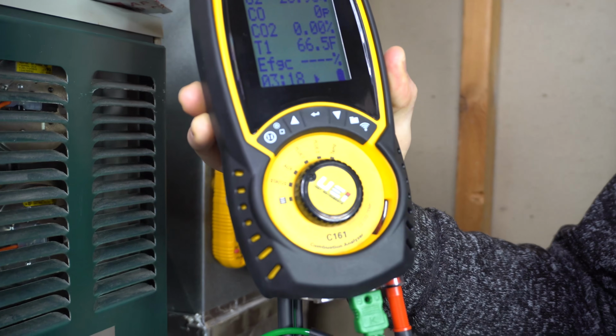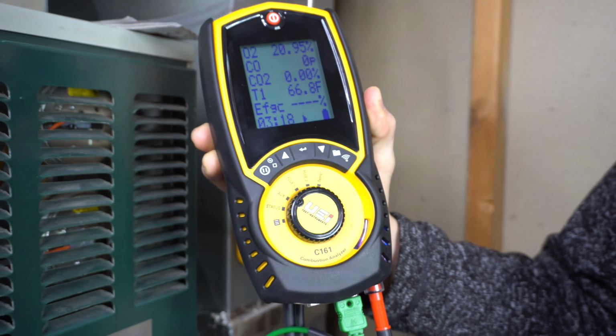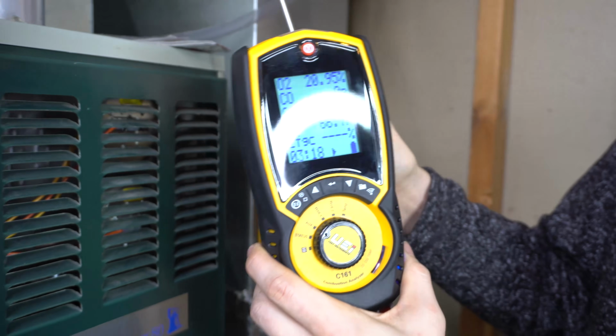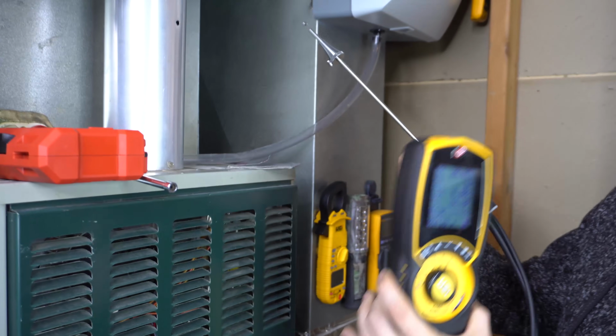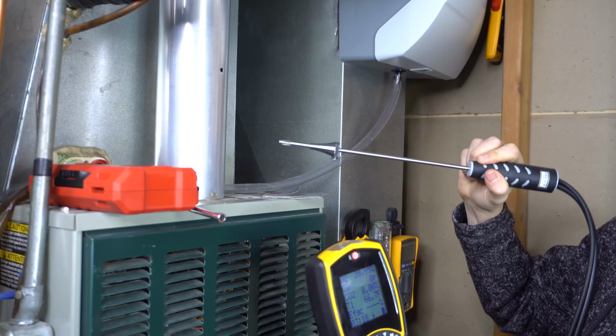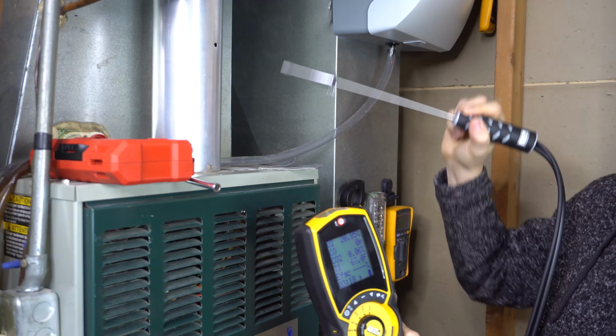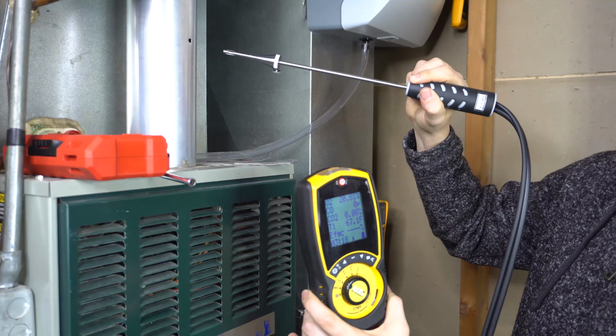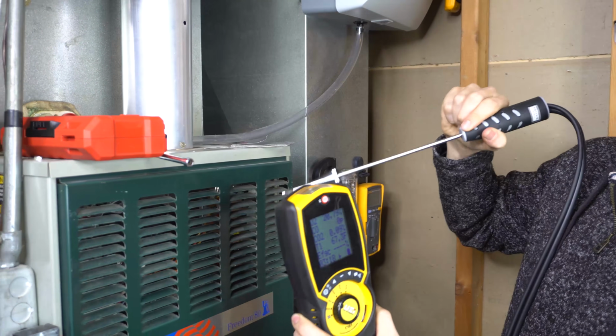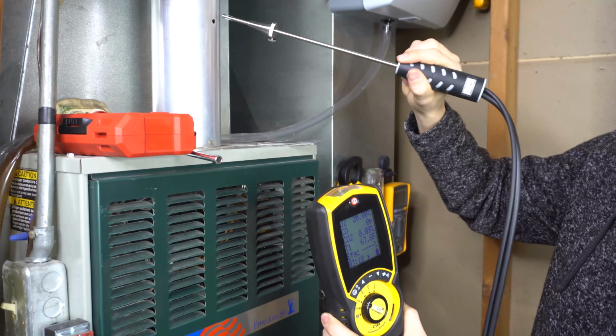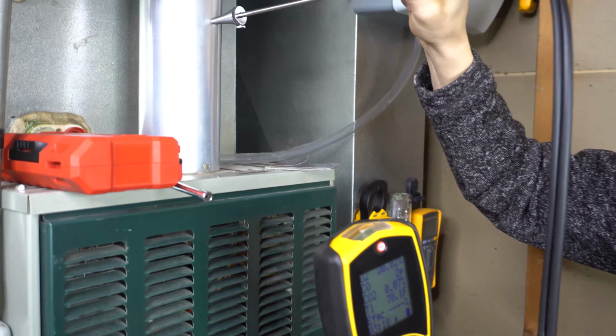The pump starts right away. And I've mentioned this before, but this is a 2-stage furnace. So after about 15 minutes of runtime, this furnace will shift up to the high stage, and my readings should change because the gas pressure goes up and the inducer motor speed goes up as well. So let's just see what we have for my low stage reading.